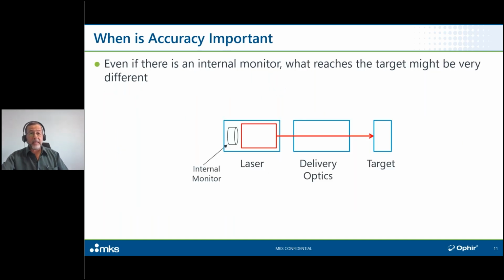Now, even if you're clever and experienced and familiar with the importance of monitoring the performance of your laser, because it's important that your process stay stable and predictable and profitable, you want to keep scrap to a minimum and so on. So you've built in an internal monitor which takes some small percentage of the laser's output and keeps track of that. That's great. In some applications, that's perfectly sufficient, but in some applications it might not be.